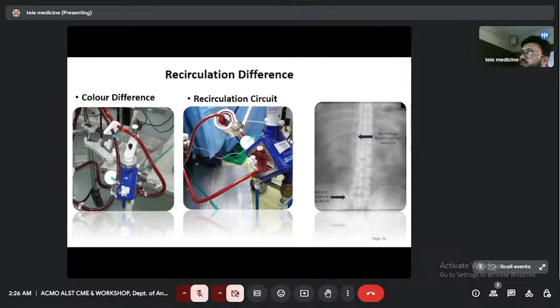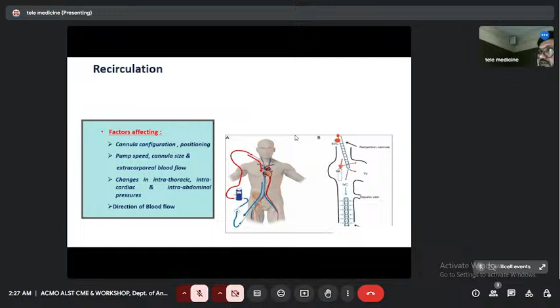Only around 20 to 30% goes to the patient. That may be because of cannula configuration, positioning of the patient, pump speed, cannula size, changes in intrathoracic and intracardiac pressures, and direction of flow. So this is because of recirculation. In refractory cases, first you have to look for the cause and reposition the cannulas. And in refractory cases, you have to put another drainage or return cannula in the patient. Like if this is bifemoral, or femoral, you have to put another return cannula in the patient.